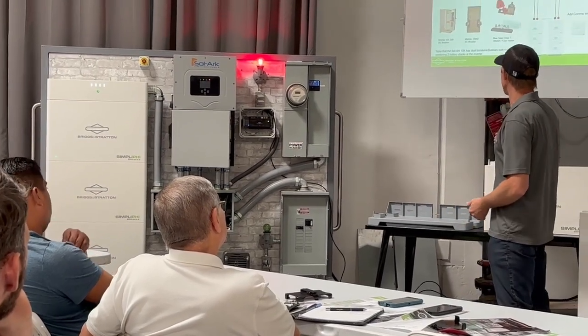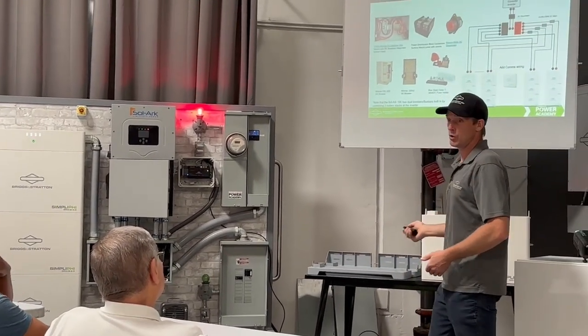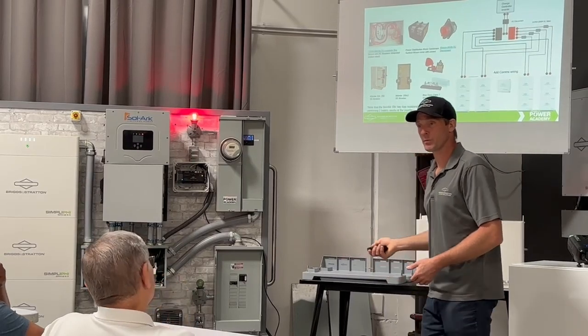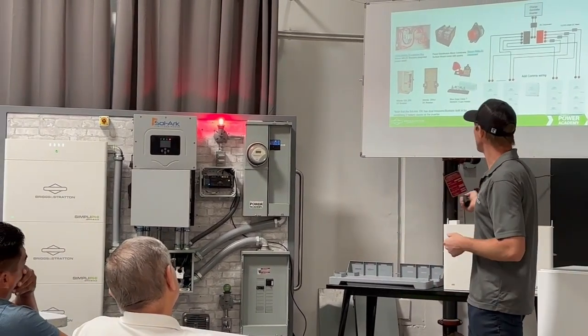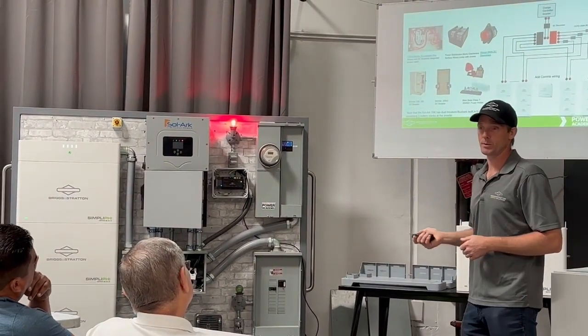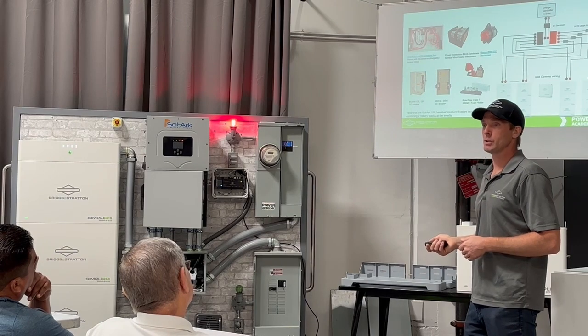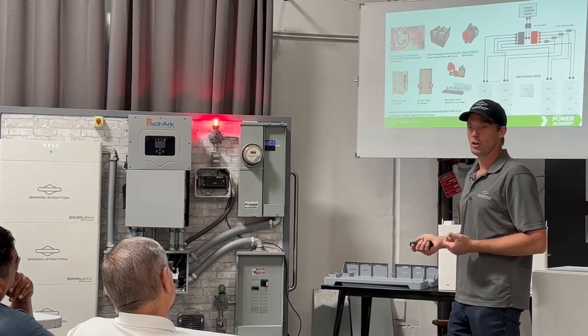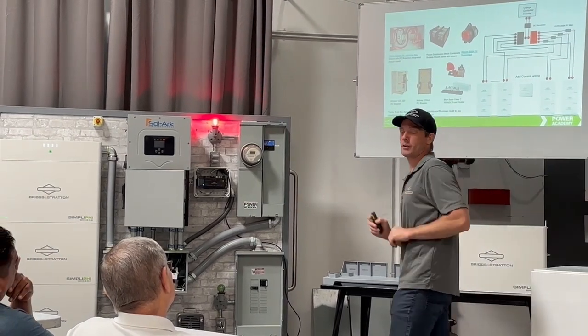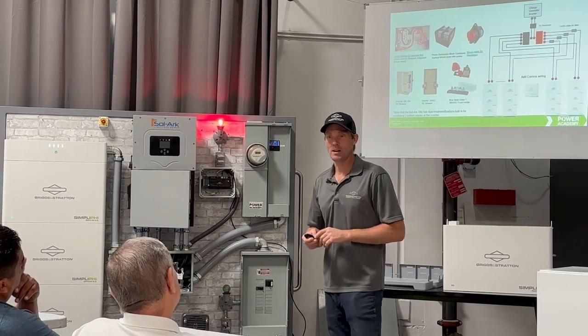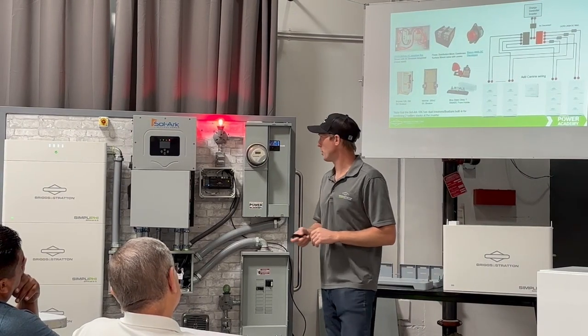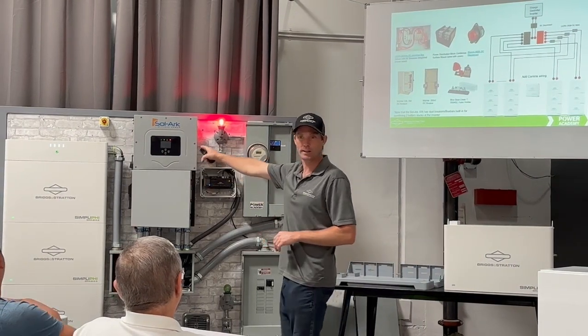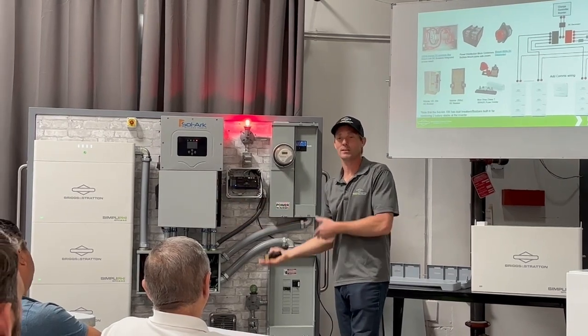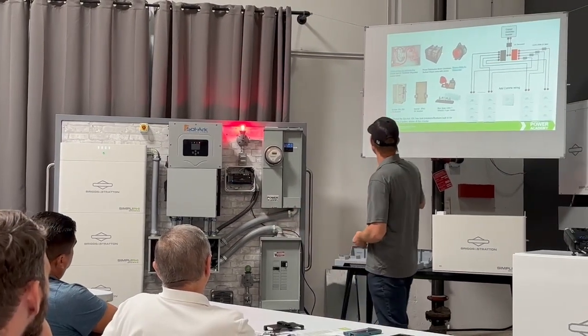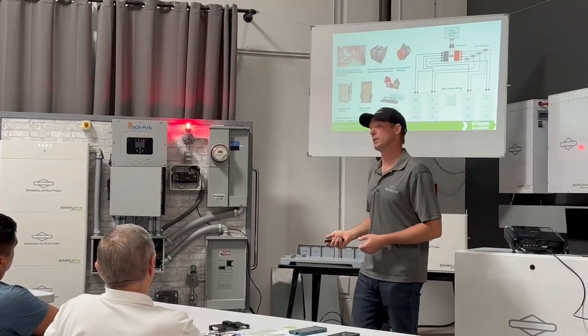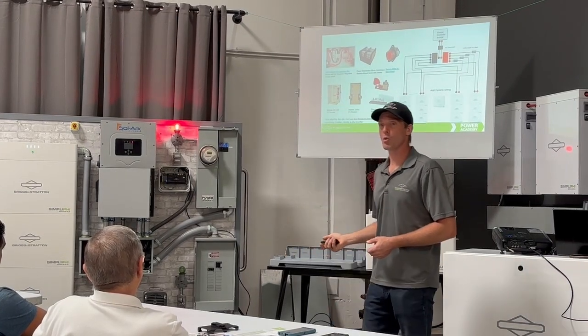Then the nice thing about these Rincon switches is they're rated to 1,000 amps, rated to 1,000 volts, and they're a 600 amp disconnect. If you go on Amazon and try to buy a switch, you'll get one rated 500 amps at 48 volts. Well, these batteries are actually operating at 55 volts, so technically you're going over that. The other thing that's nice about the Rincon switch is it's UL listed, so it's a quality product.